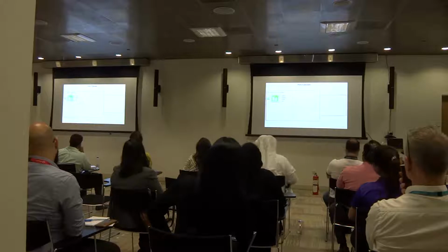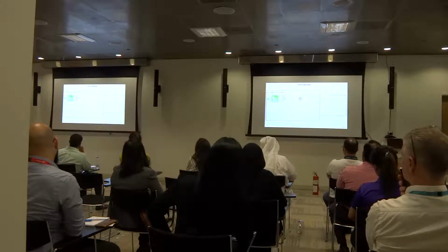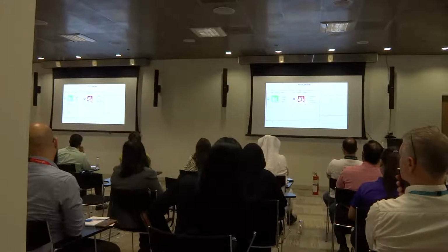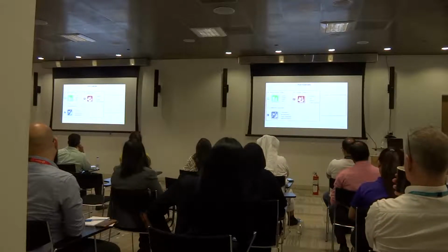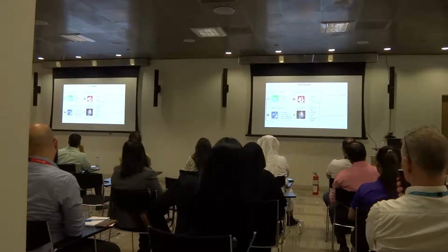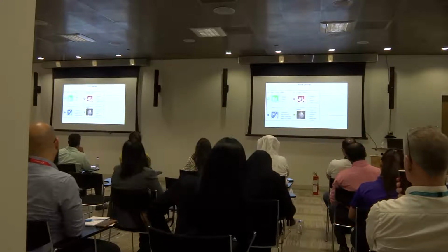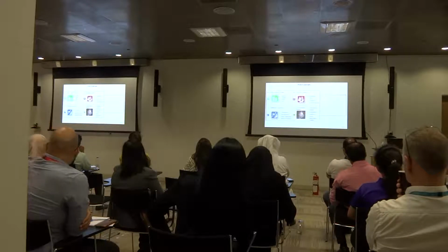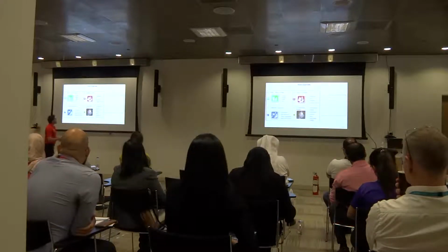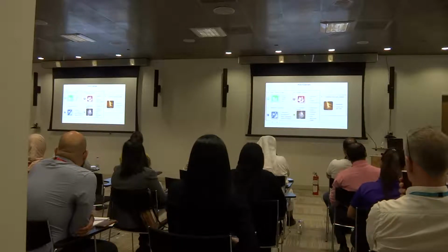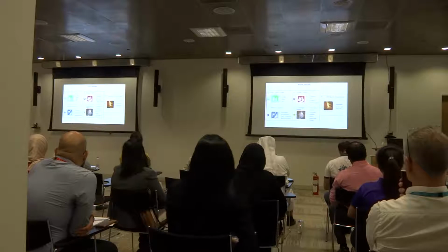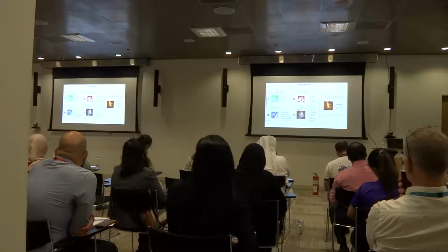Now, fire classes. Class A fire: wood, paper, ordinary combustible material. Class B fire: liquids, greases, gasoline, or other solvents. Class C fire: electrical, such as a computer, fax machine, or other energized equipment. Class D fire: metals, magnesium, potassium, titanium, or other flammable metals. How about the Class K fire? It's cooking oil, vegetable oil, or fat, any cooking materials.